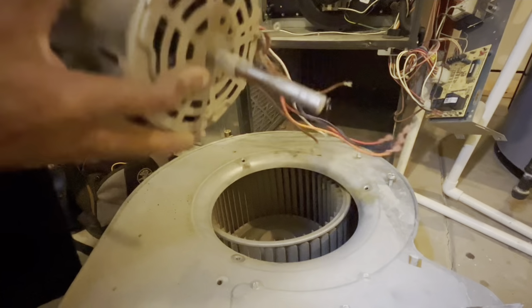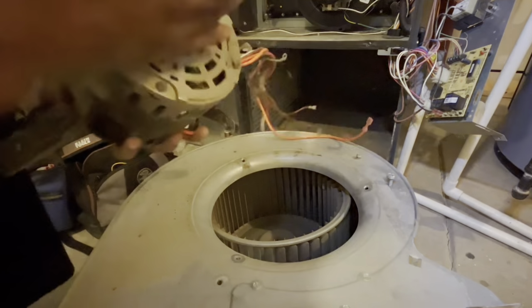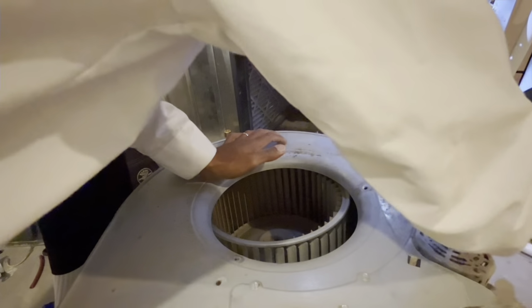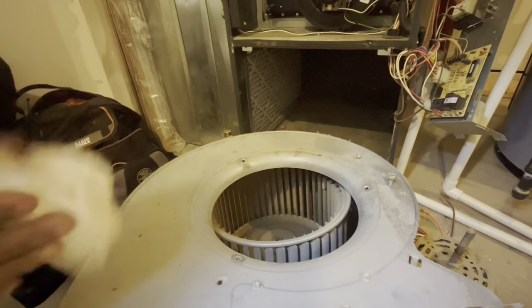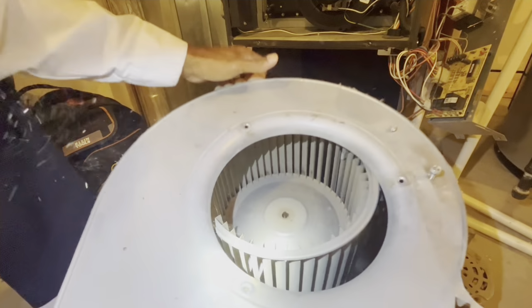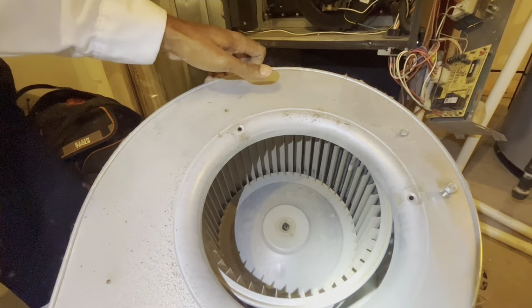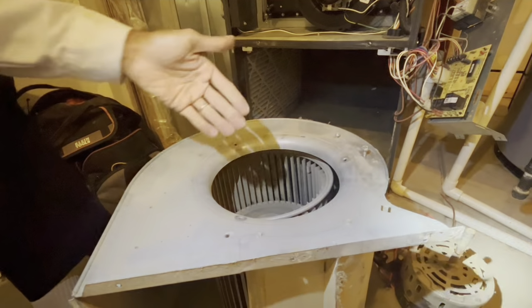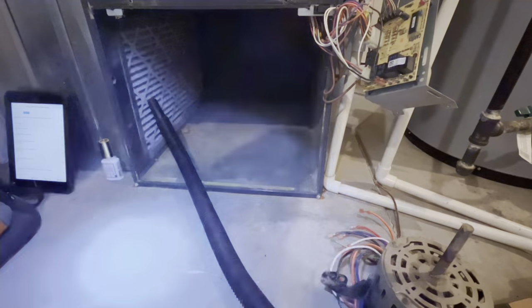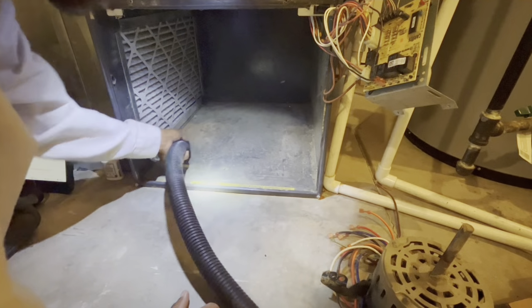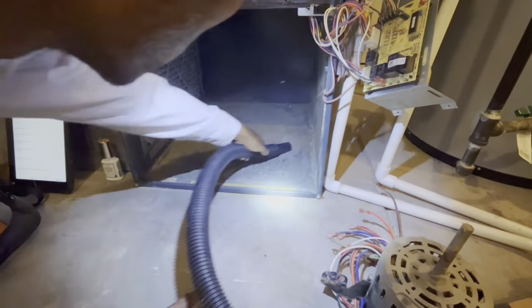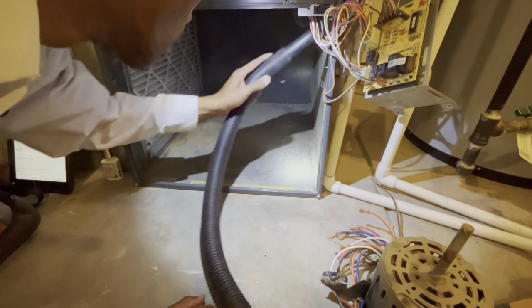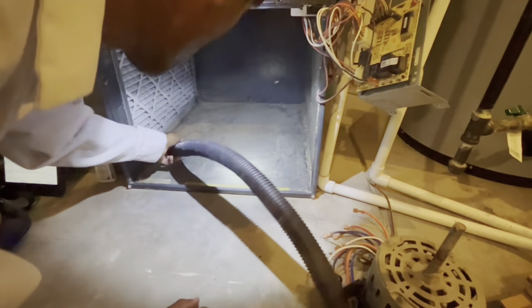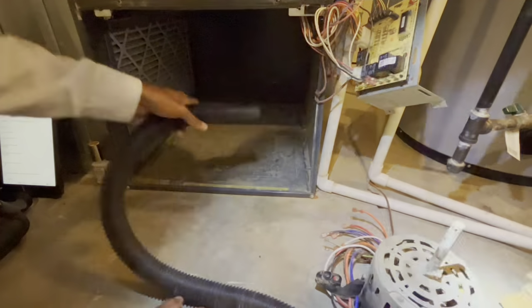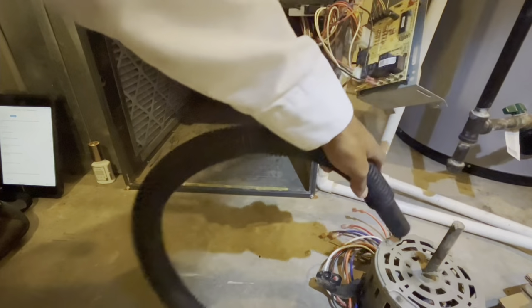So right now I'm just pulling it out to take a look at it, and I check the shaft to see how much play it has in it. If it has a lot of play in it and it's leaking oil, that motor needs to be replaced. You could keep letting it stay in there, but it's best to go ahead and replace it to give you that peace of mind that the furnace will work during the winter, or the AC will work during the summertime, because this motor is always moving air throughout the system.